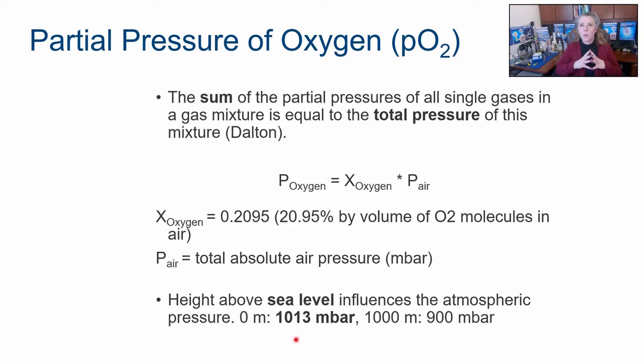Okay, so if you were to take a bioreactor and measure it in San Francisco, and then let's just pretend for a second that Star Trek's really real and we can teleport that bioreactor with all the sensors to the top of a mountain in the Swiss Alps, and we take this measurement, nothing's changed. All we've done is change the atmospheric pressure. You will actually get a very different dissolved oxygen reading, because the height above sea level, or the atmospheric pressure, significantly impacts the solubility of oxygen. This is one reason why when you get a new oxygen sensor, you will often need to calibrate it, because it is unlikely that it was calibrated at a factory that has the exact same atmospheric pressure as where you're using it.